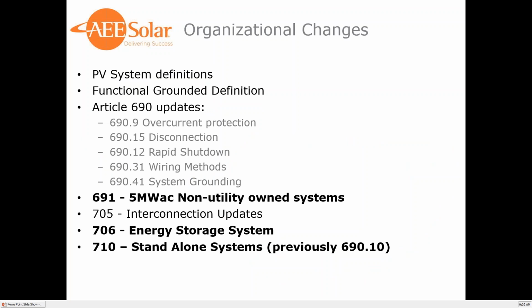So, some organizational changes to the code. The 2017 code actually went into more detail and defined the PV system. In previous code articles, there was confusion about what was actually included in a PV system, so they defined what is included in the 690 section. Hopefully it'll clear up a lot of discrepancies. They added a new definition for functionally grounded systems, which we'll go into in more detail, which has some effects on wiring, overcurrent protection, and other things that we'll look at.